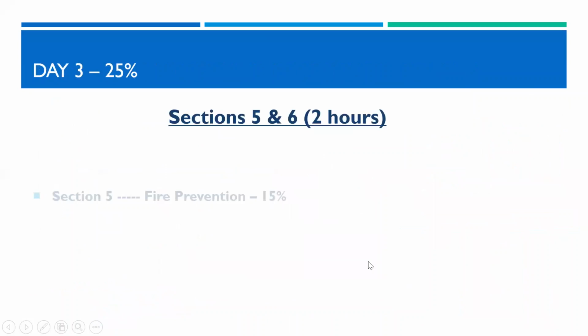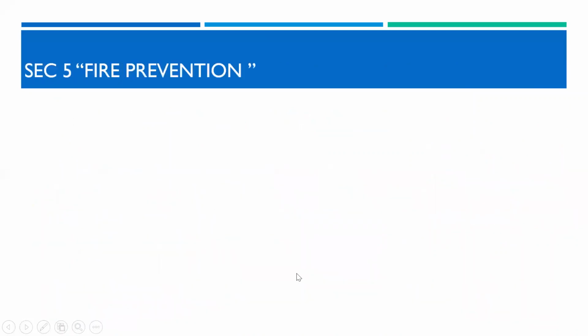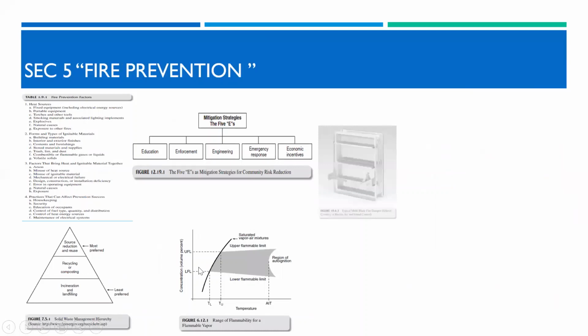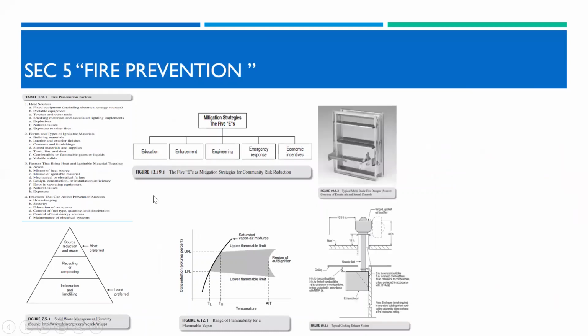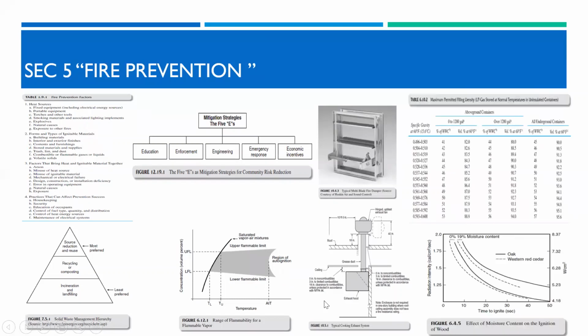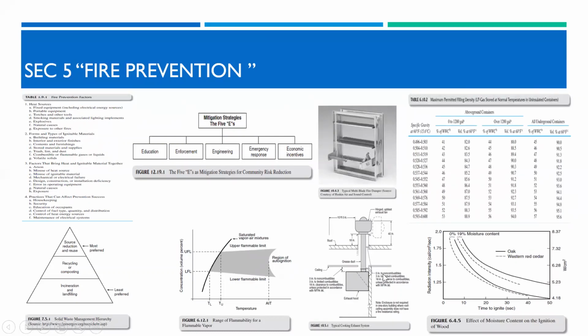Here you have 2 sections: fire prevention and facility hazard management. As we see here, in fire prevention, we reduce the waste. We have 4 factors for prevention. We have mitigation strategy, and we have upper flammable limit and lower flammable limit in order to avoid auto ignition. We have components of HVAC systems like fire dampers, kitchen cooking hood systems, and exhaust systems. And we have here flammable liquid or combustible liquid container storage with separation distance and quantity.